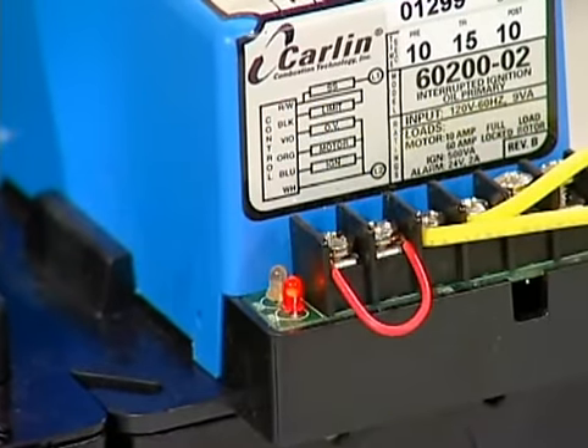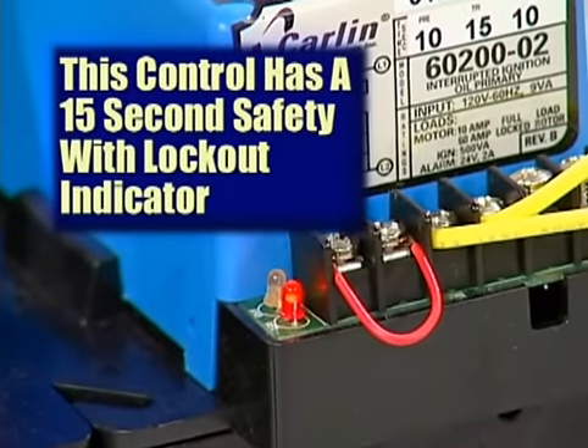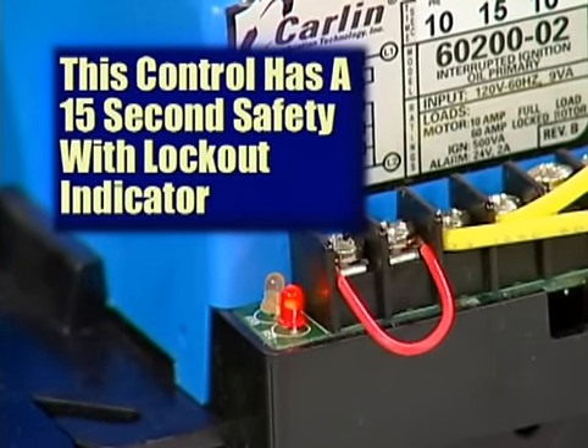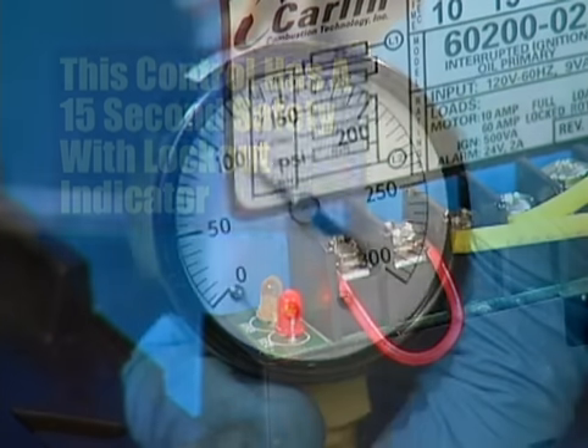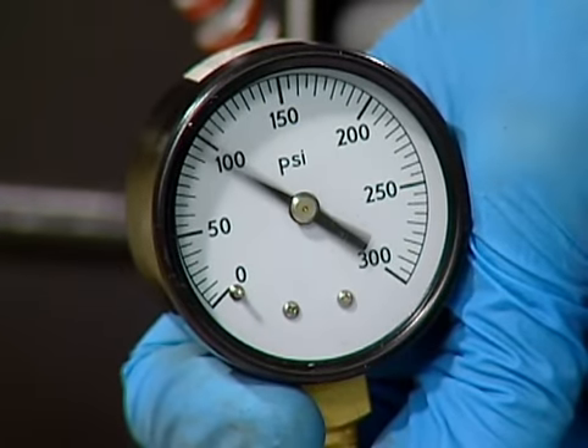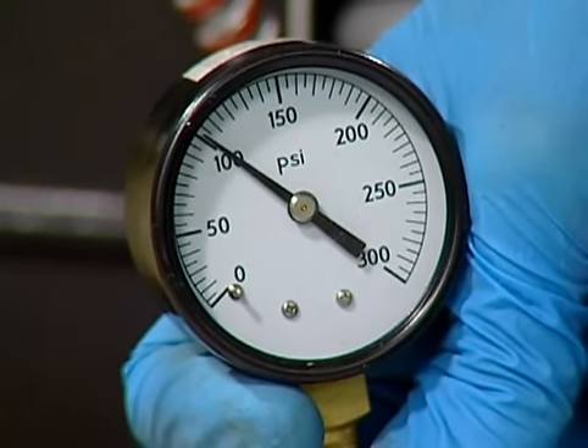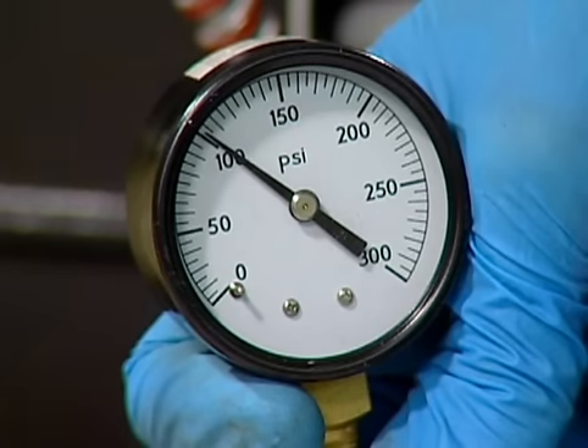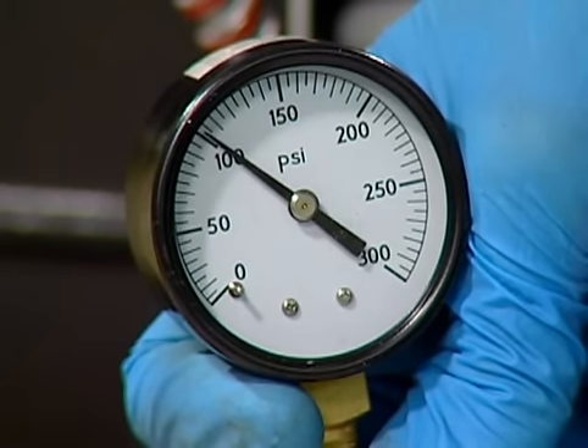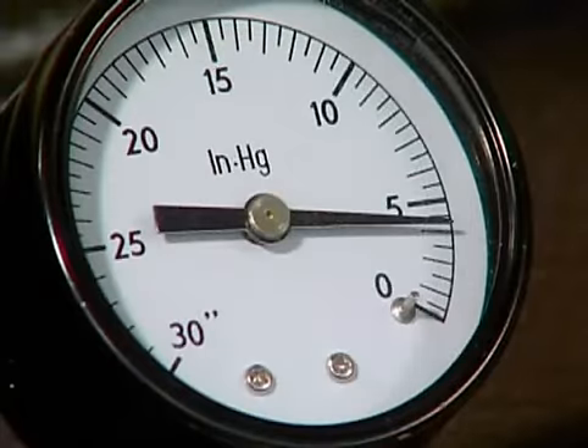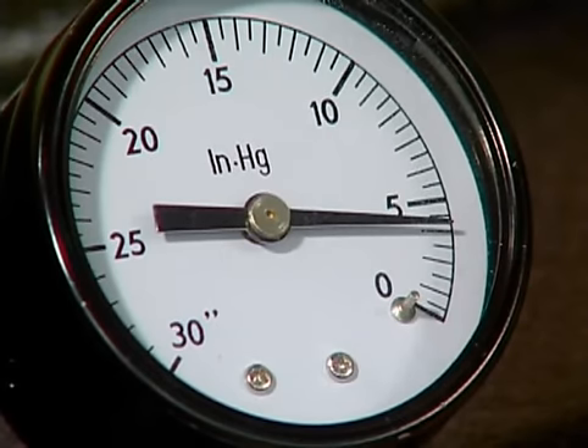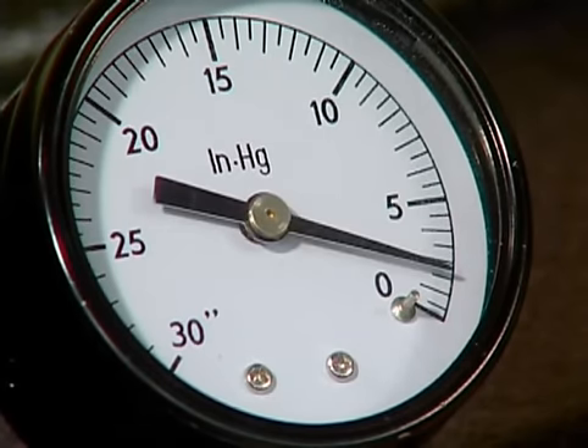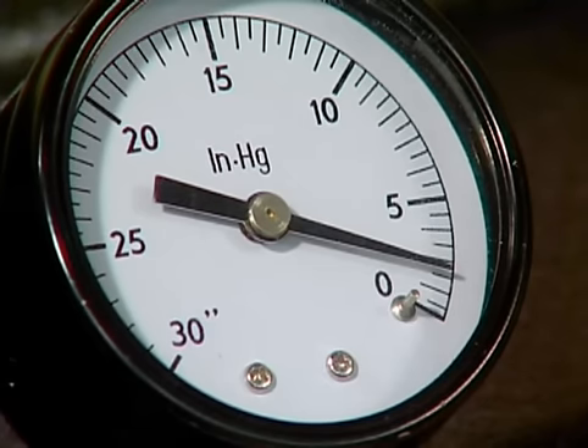After adjusting the pump back to its proper setting, wait until the unit shuts off on safety and verify the safety timing. When the unit shuts off, the pump pressure should drop no more than 15 to 20% and then hold steady. If the pressure continues to drop, the pump has a bad cutoff and requires replacement. At shutoff, the vacuum should drop slightly and hold. If it drops to zero, there is a problem with the pump, the OSV valve, or the oil line.